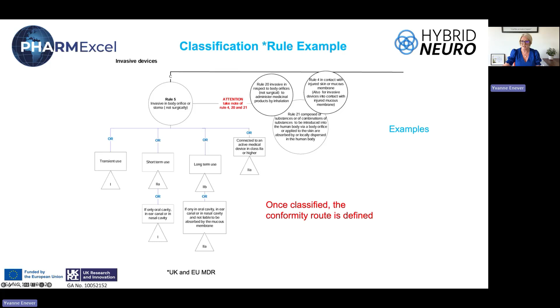But if we're just taking a general invasive device, you'll start with Rule 5, and then you ask yourself questions. Am I just going to use this for transient use? Or is it going to be short-term use? Or do I intend for it to be used longer term? If I intend for it to be used longer term, you can see quite clearly here, it's classifying my device as a class 2B. But if I'm only intending my device to be used in the oral cavity or in the ear canal or in the nasal cavity, then actually that's going to be a class 2A. So it's about being really familiar with how these rules work and how they apply to your device.